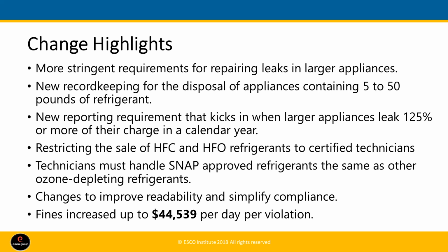Also, now the EPA is restricting the sale of HFCs and HFO refrigerants to technicians that are certified under Section 608 or 609 of the Clean Air Act. Technicians must also handle HFC refrigerants in appliances containing HFC refrigerants in the same manner that they have handled other ozone depletion refrigerants in the past. EPA has also improved the readability and simplified some of the compliance regulations, especially dealing with the larger equipment.